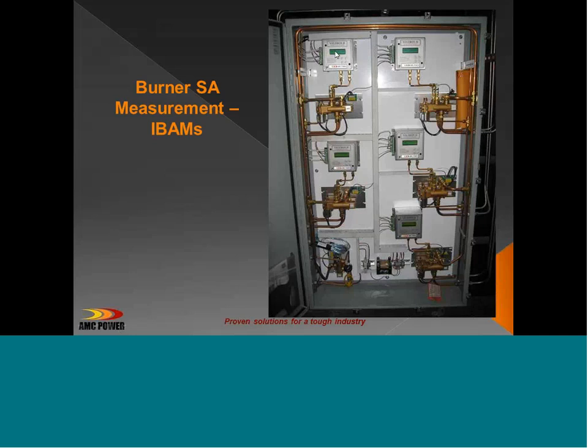There's a timer that goes off within the transmitter, or it can come from the DCS, and tells this to do its purge. It locks and holds its signal to the DCS. It says it's in purge mode, and it shuttles the valves, which brings instrument air to each of the pitot tubes and cleans them out.